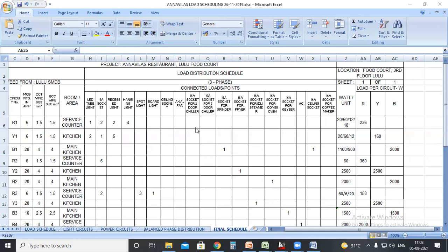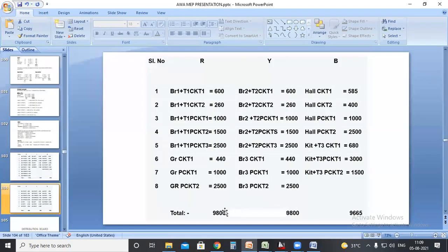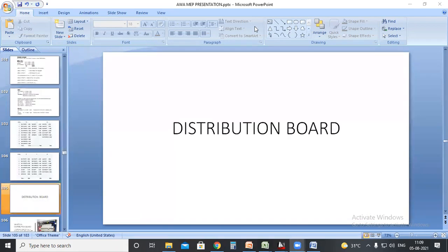While taking a three-phase connection, we get all the phases together, that means 4 wires will be coming, including the neutral. But if taking a single phase connection from the utility pole, you will have only one phase and neutral. In that case, the type of distribution board shall be a single phase distribution board, that is SPN, single pole neutral, known as SPNDB. So that is category one, the single phase distribution board.